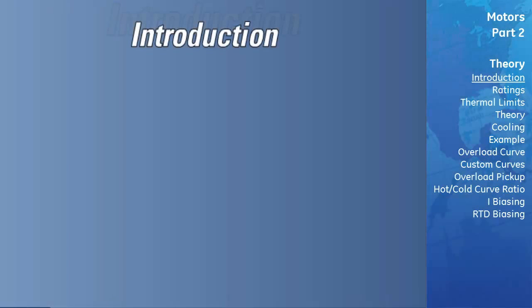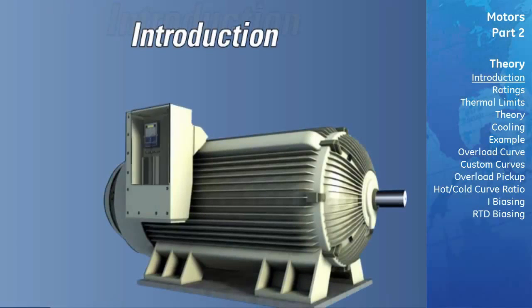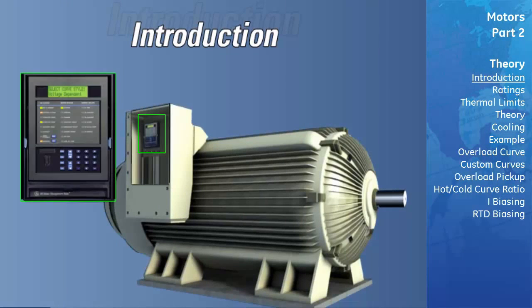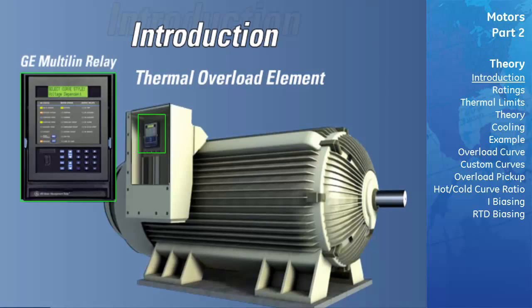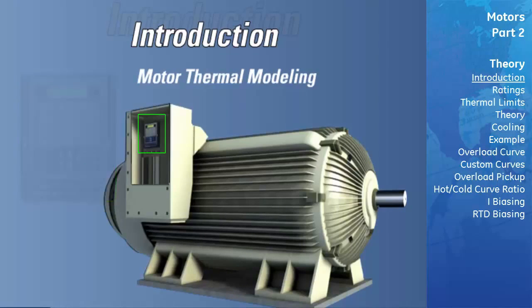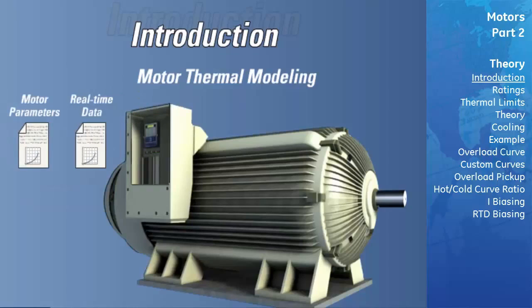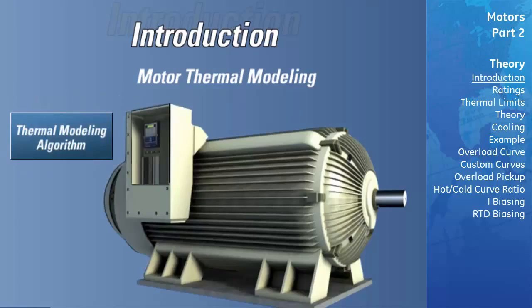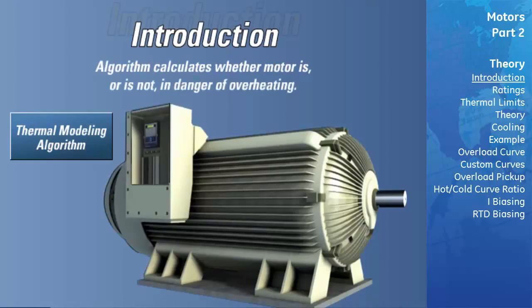Motor Thermal Modeling. The primary motor protective element within a motor protective relay is the thermal overload element, and within GE Multilin Relays, this is accomplished through motor thermal modeling. The thermal model uses motor parameters supplied by the manufacturer in addition to real-time data, such as motor current, as inputs to a thermal modeling algorithm. The algorithm then calculates whether the motor is or is not in danger of being overheated.